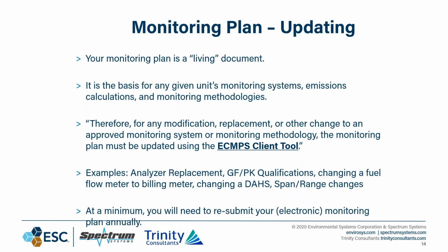Now let's get into updating the monitoring plan. Like Adam was talking about, this is meant to be a dynamic document, a living document. It is the basis for your monitoring systems, your unit's monitoring systems, your emissions calcs, your monitoring methodologies. And as a direct quote, for any modification, replacement, or other change to an approved monitoring system or monitoring methodology, the monitoring plan must be updated using ECMPS through the platform.